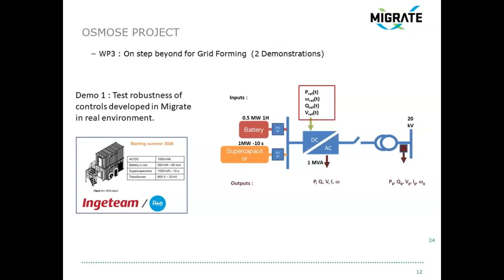And on the DC part, we have a hybrid system with a battery and a supercapacitor. Why did we do that? Because we considered that the battery would behave roughly as a grid following unit, and the supercapacitor would behave as grid forming. So it's the supercapacitor that handles this inertia aspect, dealing with all the fast transients and not aging the battery. The battery can also be considered as an old model that's been upgraded with a supercapacitor.